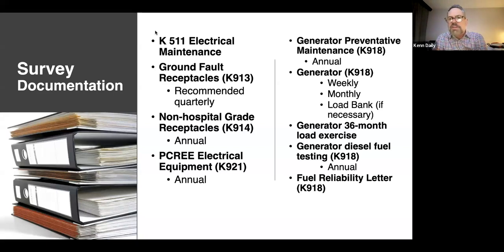But this is in lieu of having to put a secondary form of fuel in, which most of the time with natural gas generators, you will put in a propane tank. There have been situations in some states to put propane tanks in to back up your generator's fuel source, so that if your natural gas would fail, propane in the fitting is very similar. So it burns very similar, so it works quite well. But this is so you don't have to do that. Some of you may have done this, but it's not necessarily required.